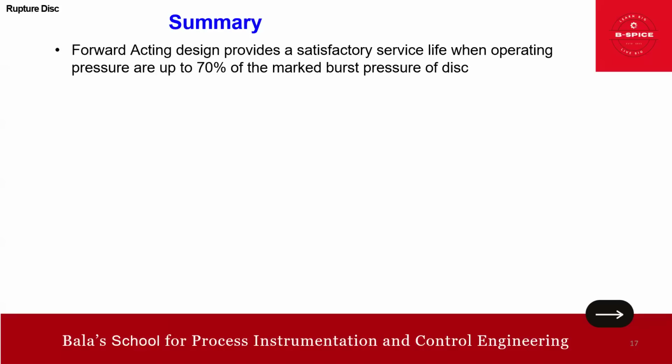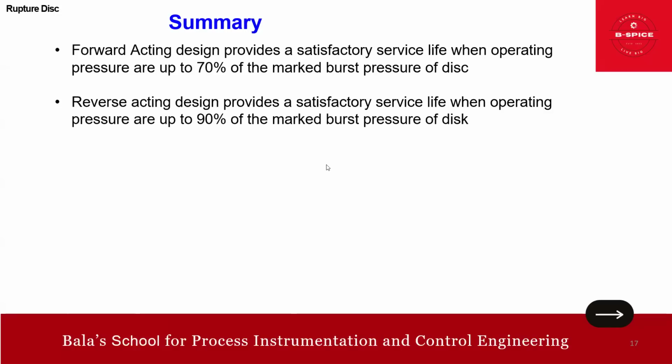Right, friends. So now I also want to give you a summary. Forward acting design provides a satisfactory service life when operating pressure is up to 70% of the marked burst pressure of the disc. Reverse acting design provides a satisfactory service life when operating pressure is up to 90% of the marked burst pressure of the disc.